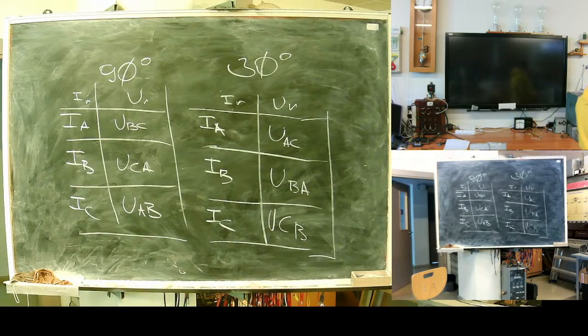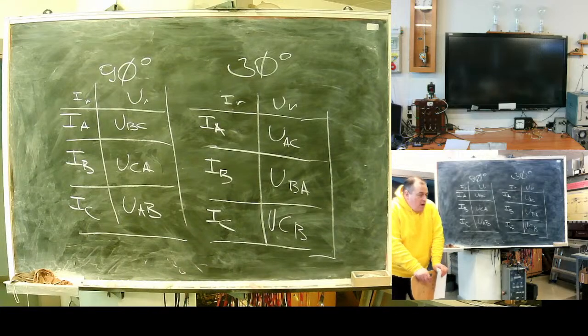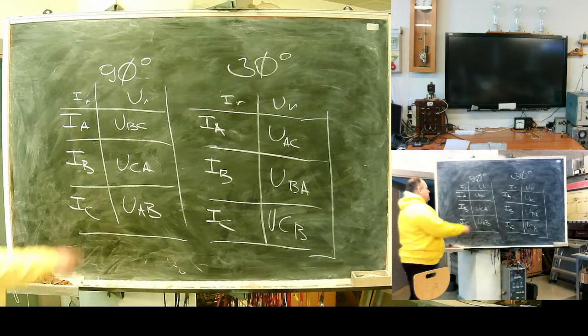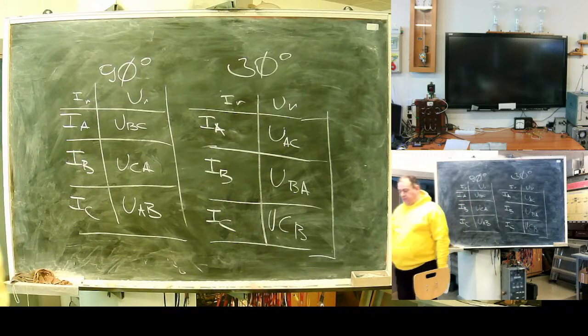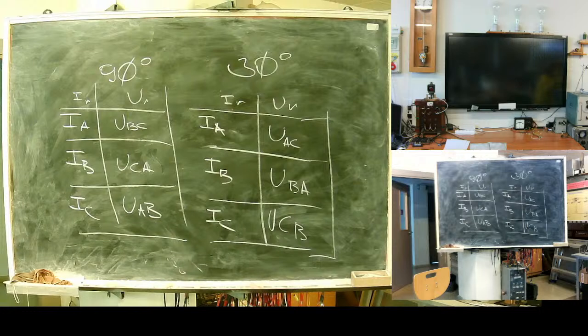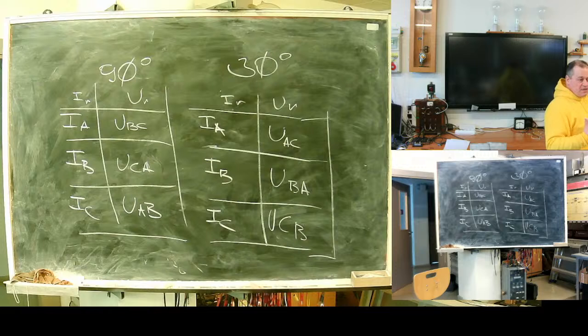If you perform a simulation on both schematics, you will find interesting things. In case of a three-phase fault, everything works fine in both cases. In case of a line-to-line fault, only in these schematics do all relays operate safely. In 30 degrees schematics, one of the relays sitting on the lagging phase may not operate. It's not 100% guaranteed, but it's less reliable.